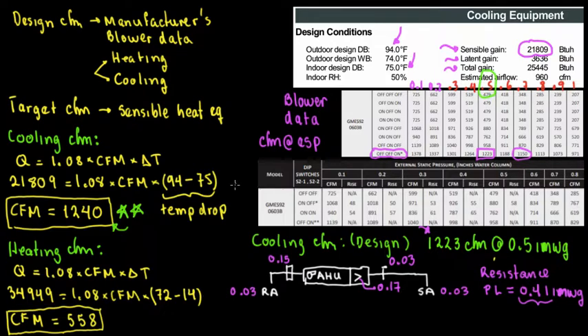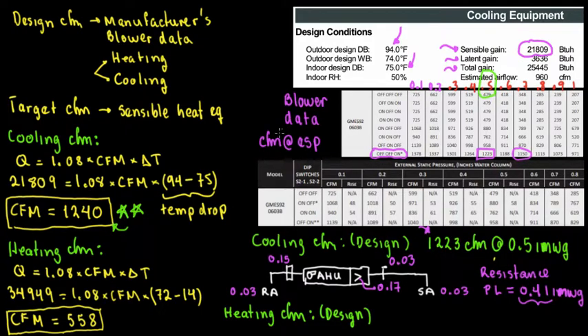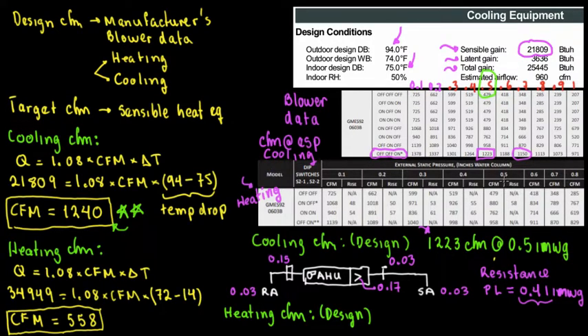Now for the heating design CFM: the manufacturer provides separate blower data for heating and for cooling. It's better to say 'heating' rather than 'heat' because 'heat' is more generic — when doing a heat load calculation, we talk about both cooling load and heating load together. The design heating CFM is selected from the manufacturer's blower data at 0.5 inches of static pressure.